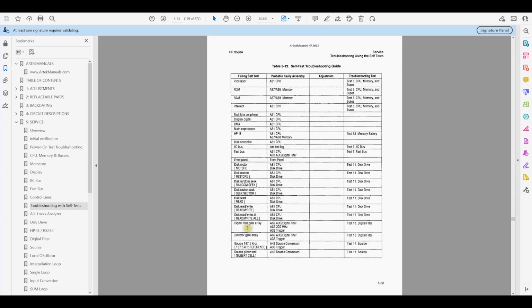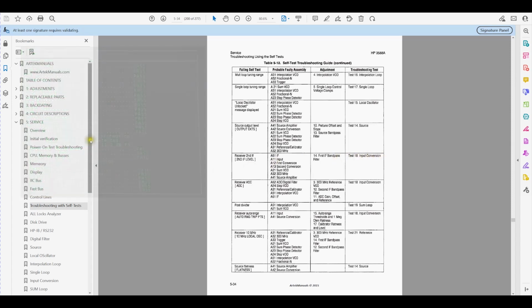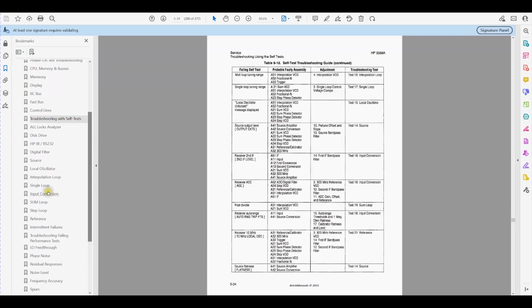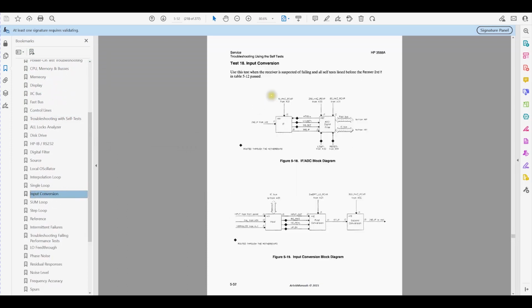Go to 5-12. We note the first failure is the second intermediate frequency. Probable faulty assemblies are the A61 IF, followed by the A11 input. The suggested test to perform is test 18, input conversion. Go down to 5-52. Test 18, input conversion. Says to use this test if all prior self-tests have passed. This looks like it matches our case.